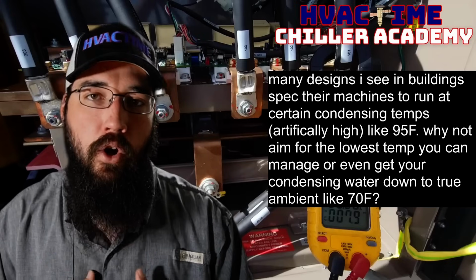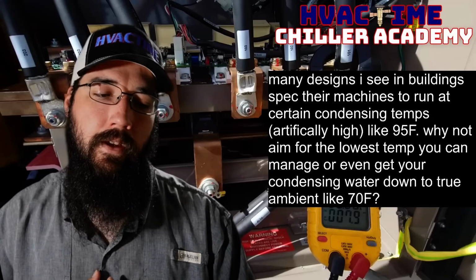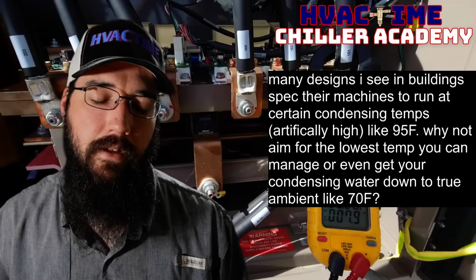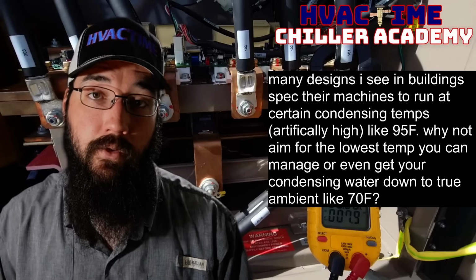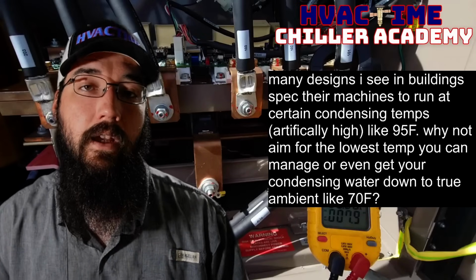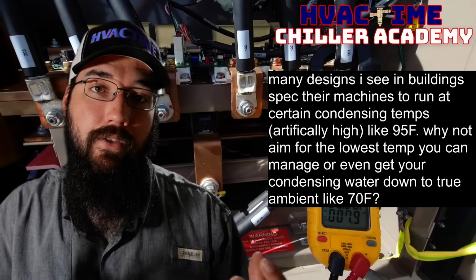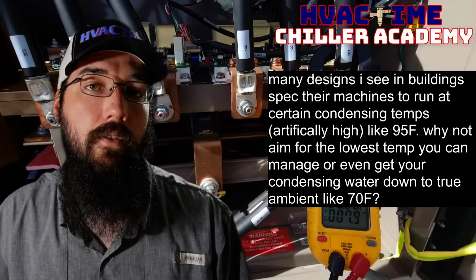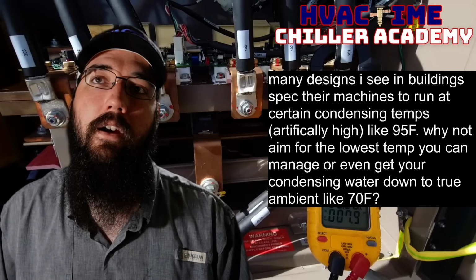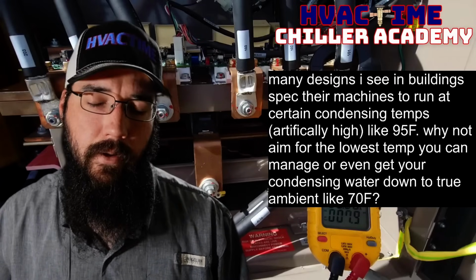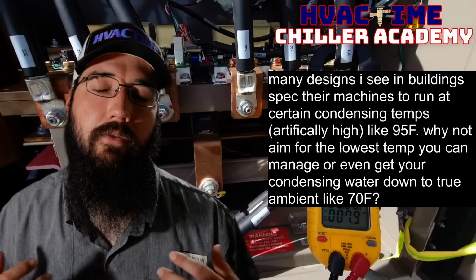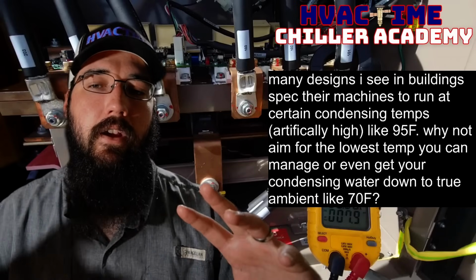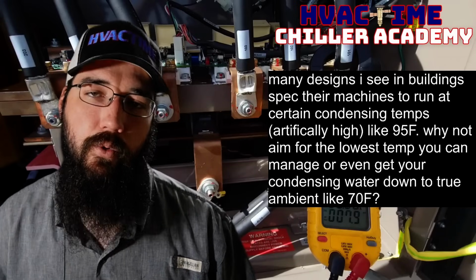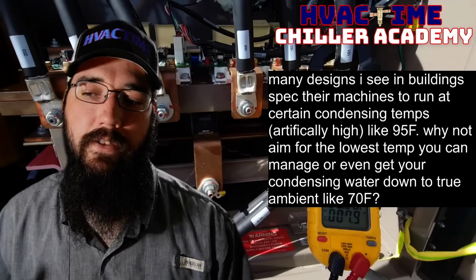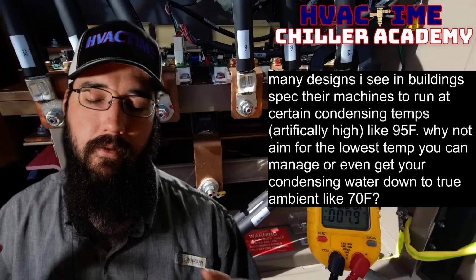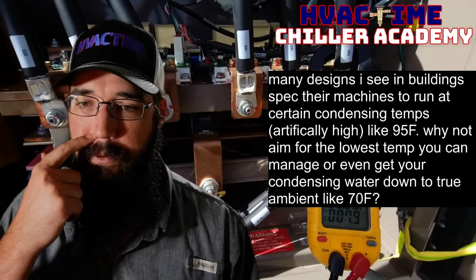And what I have personally experienced with some of these is they do believe in raising condenser water temps. Their idea is they're trying to draw load off of the cooling tower and make the fans run slower. That is the main concept they've always given me: they want the fans to run slower on the cooling tower, and so less amperage, less energy, right? As if it was that simple. I'll get to that in a moment.